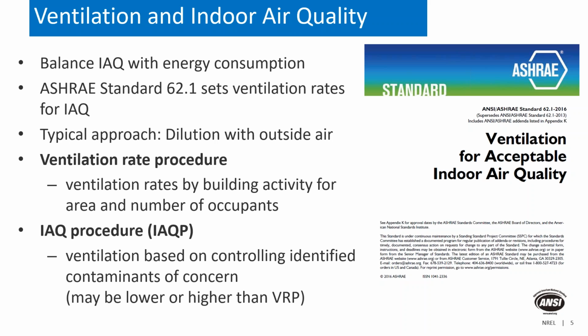You can also follow the IAQ procedure or IAQP, and that allows you to set the ventilation based on controlling your identified contaminants of concern. You have to identify the contaminants of concern and then show through mass balance equations that you are maintaining those under the limits that are specified by your authority having jurisdiction. And that may actually raise or lower the ventilation rate depending on what your sources of pollution are.